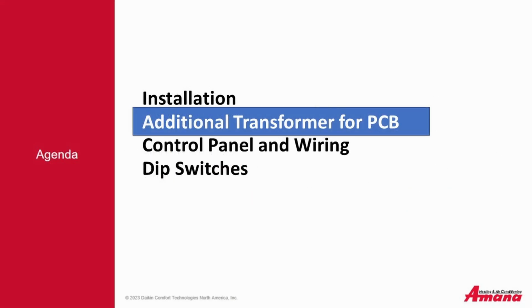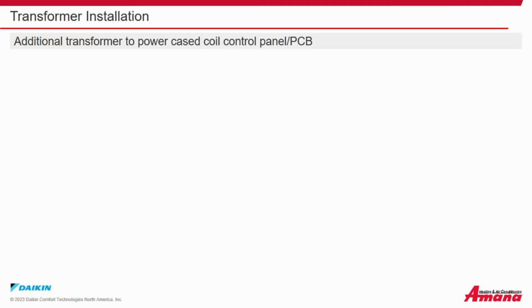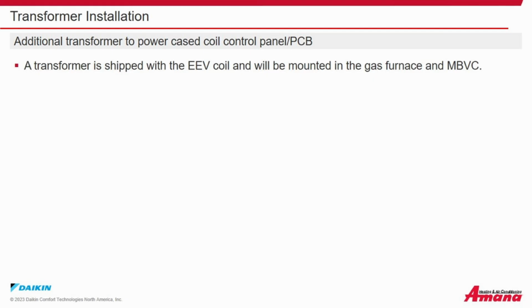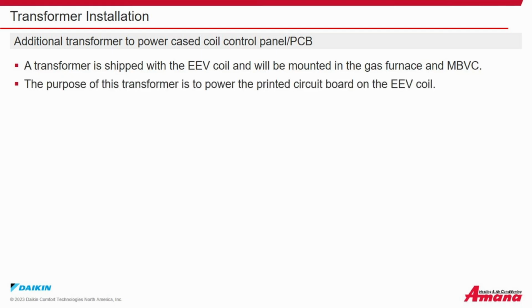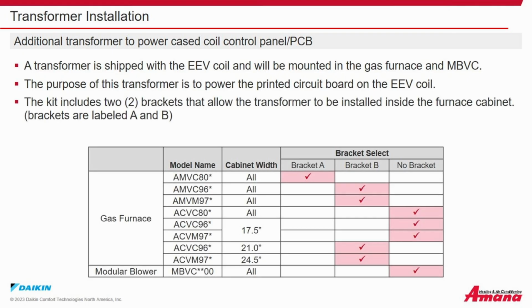Additional transformer for the printed circuit board. Transformer installation. Additional transformer to power the cased coil control panel printed circuit board. A transformer is shipped with the electronic expansion valve coil and will be mounted in the gas furnace and the MBVC. The purpose of this transformer is to power the printed circuit board on the electronic expansion valve coil. The kit contains 2 brackets that allow the transformer to be installed inside the furnace cabinet. Brackets are labeled A and B.